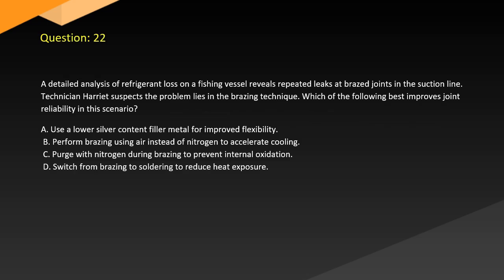Question 22. A detailed analysis of refrigerant loss on a fishing vessel reveals repeated leaks at brazed joints in the suction line. Technician Harriet suspects the problem lies in the brazing technique. Which of the following best improves joint reliability in this scenario? A. Use a lower silver content filler metal for improved flexibility. B. Perform brazing using air instead of nitrogen to accelerate cooling. C. Purge with nitrogen during brazing to prevent internal oxidation. D. Switch from brazing to soldering to reduce heat exposure.